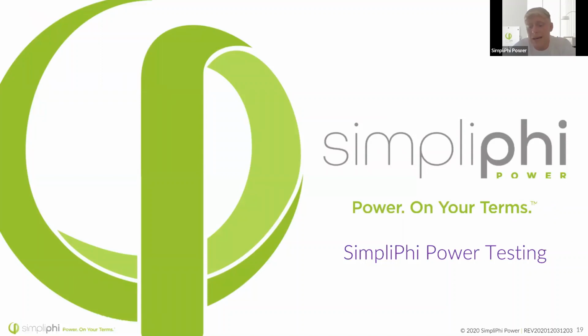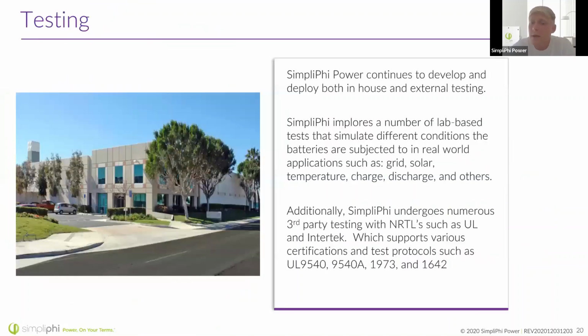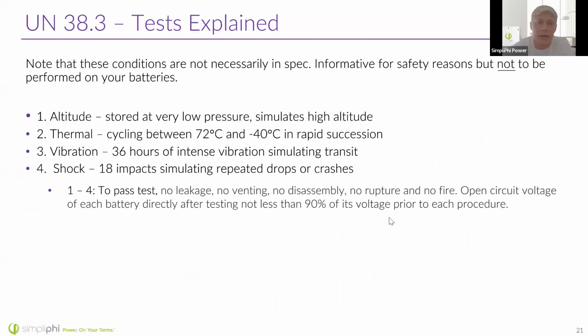So as far as the testing that has been done, we do our own internal quality testing and lab testing as far as charge and discharge. I can't say that we necessarily perform very intense, rigorous vibration testing or altitude testing at our own facilities, but that's something that is done elsewhere, like the UN 38.3 test. This is required if you want your batteries to be able to board an airplane. So if you want to be able to airship your batteries, you've got to get this UN 38.3 test.